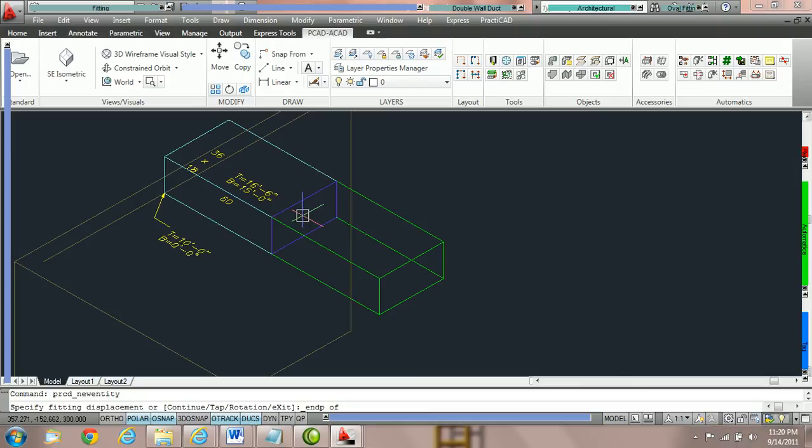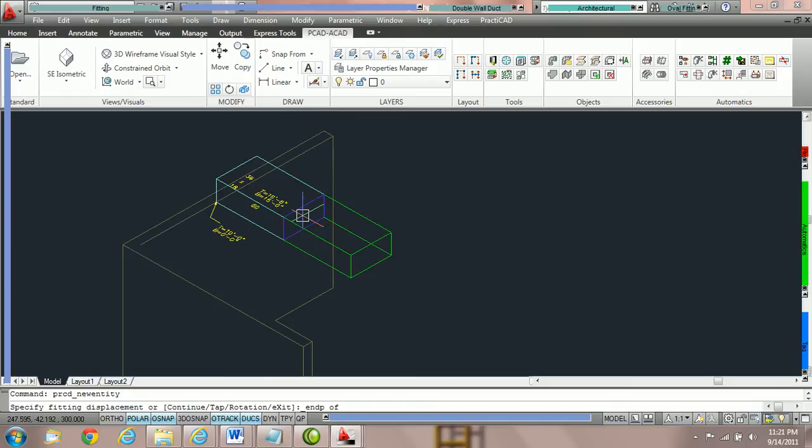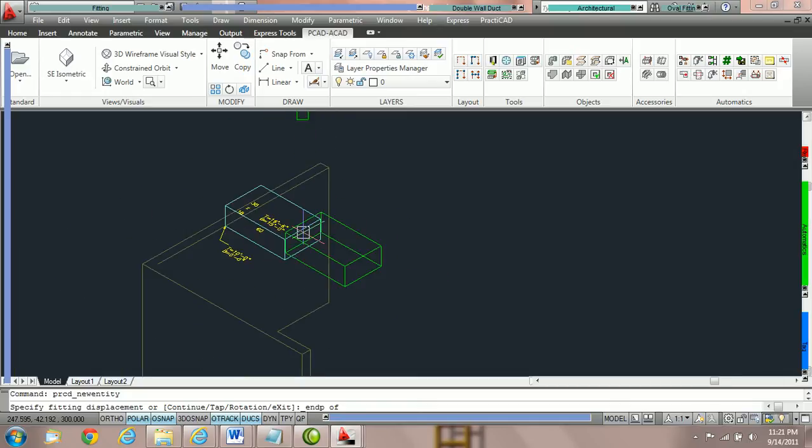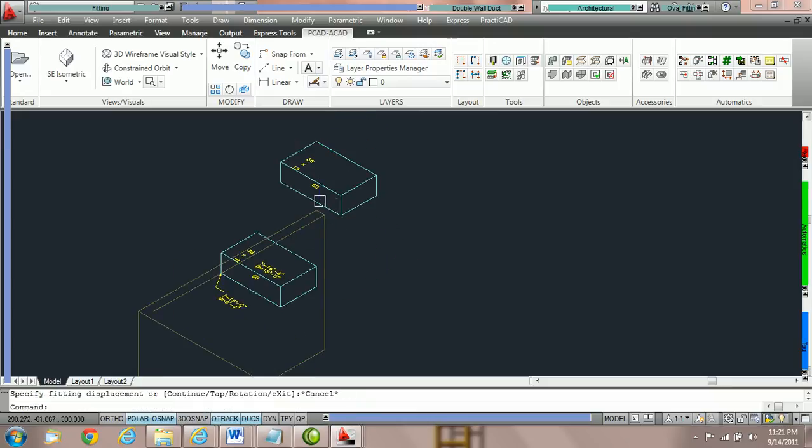Practicad would normally snap this duct to this fitting and it would pick up the elevation. However, Replace Z overrides that feature. So you can see here, if I zoom out, you can see that AutoCAD is actually holding a node about 10 feet above where we want to attach. So if we were in plan view and I actually clicked, we would go to place the duct on the drawing. Now here it's obvious in isometric that it's snapped to a node 10 foot above.